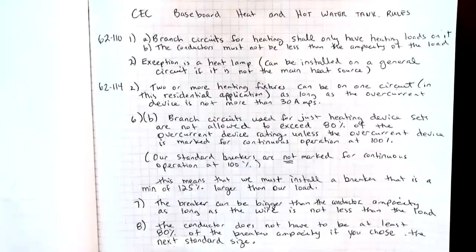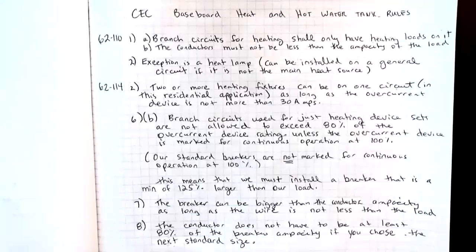Subrule 7 says the breaker can be bigger than the conductor ampacity, as long as the wire ampacity is not less than the load. Subrule 8 says that the conductor ampacity does not have to be at least 80% of the breaker ampacity if you have chosen the next standard size — so if that is the next available size, the breaker can be bigger than the wire ampacity and the wire does not have to be 80% of it.